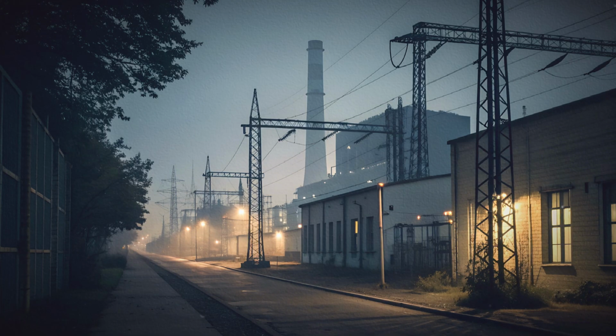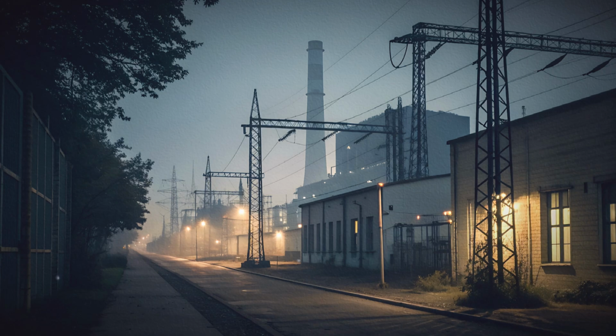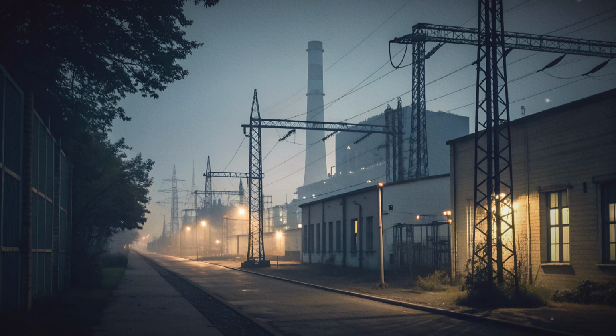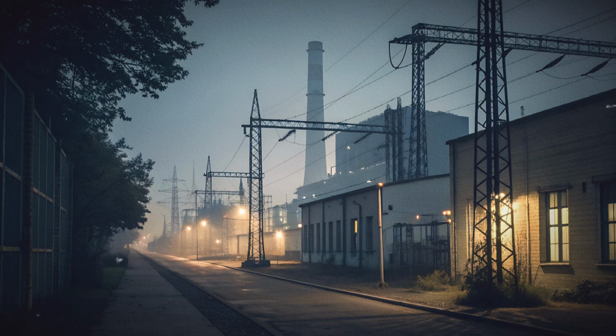Generators also manage voltage and reactive power. Voltage at a node in the grid is influenced by real power flow, reactive power flow, and the electrical characteristics of lines and transformers. Synchronous generators adjust their field excitation to absorb or supply reactive power.